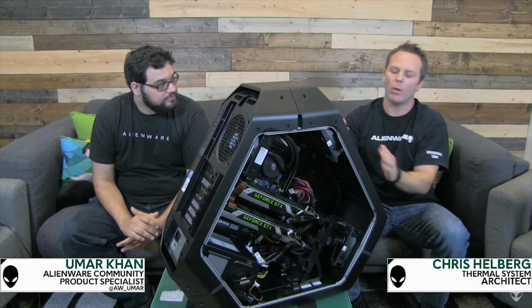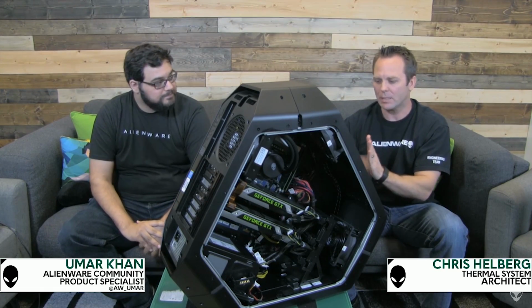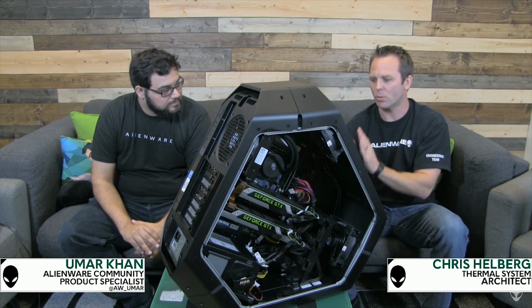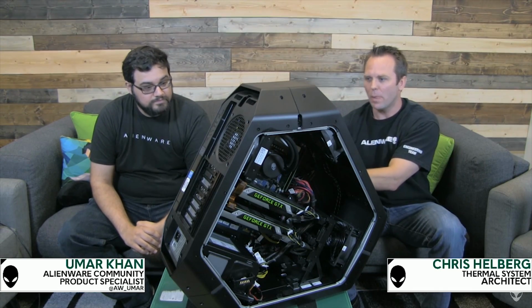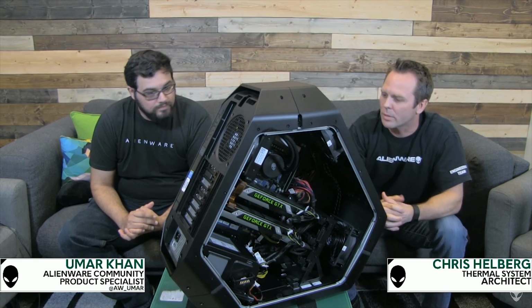But with this design, it's just pushing up and out. That wall we call a pressure impedance. If the fan has to overcome that additional back pressure the wall is creating, it'll run hotter, or the fan has to run faster. So with this triangle design, we reduce the back pressure to all the blowers, all the fans in the system.